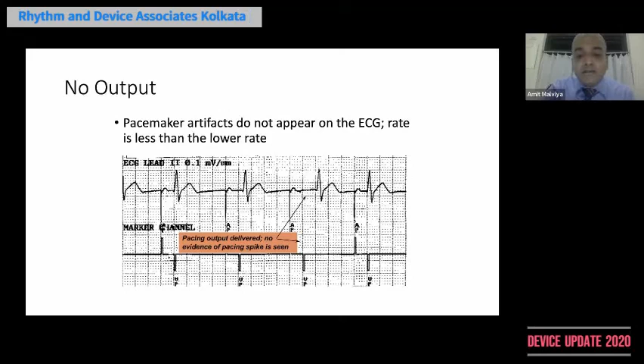So as you can see, the difference from non-capture is that there is no pacemaker artifact on the surface ECG, whereas the marker channel might still show a pacing artifact. So no output is usually caused by poor connections, lead failure, battery depletion, or circuit failure.